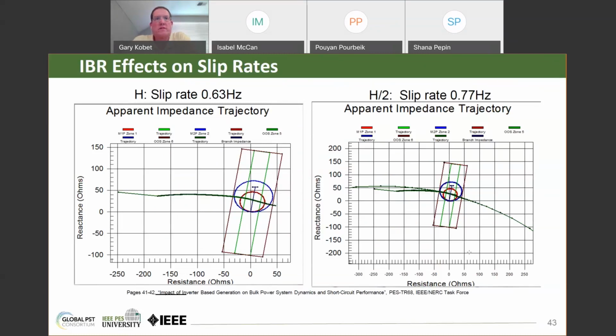On the left, the slip rate was 0.63 hertz, and in this case, there was one slip cycle. But on the right, with an increased amount of inverter-based resources in the same system, in fact half of the conventional generation replaced with inverter-based resources, so the inertia constant is half of what it was, the slip rate has increased to 0.77 hertz, and two slip cycles occurred for the same time period in the transient stability study.